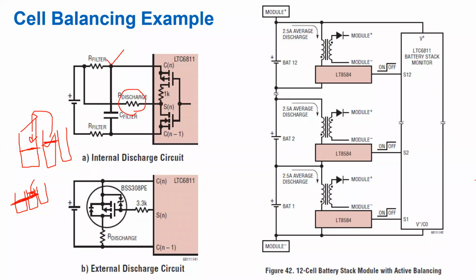In case of active balancing, we have to attach a separate chipset. Like for Analog Devices, we have a chipset LT8584, and ferrite cores that you have to use across each of the modules. The current average that you can have is higher in this case. In case of internal discharges, generally you can do about 100 milliamps of discharge.